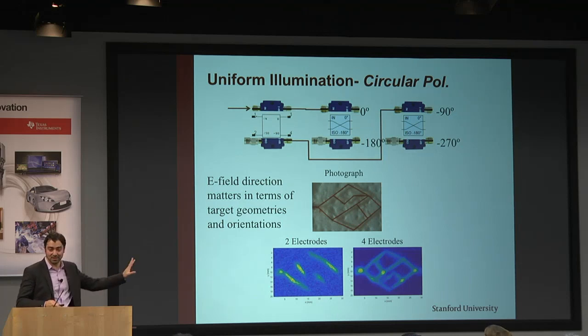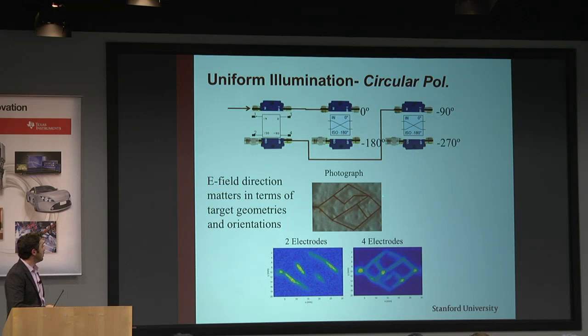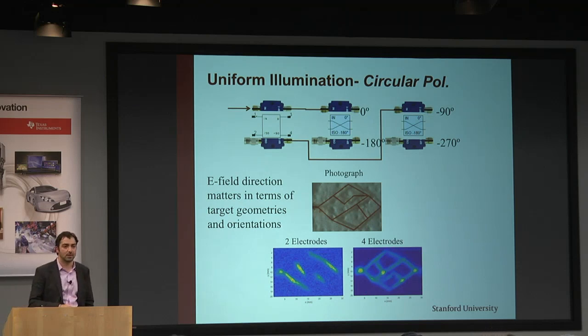So we looked at capillaries again. These are very small capillaries, and we saw if you apply a simple unipolar, sort of a unidirectional polarization, you won't be able to see orthogonal vessels. But if you apply the right polarization, orthogonal, if you do it with circular polarization, you can actually see both blood vessels. Right? So that's one of the things you have to take into account when you're designing an E-field excitation.